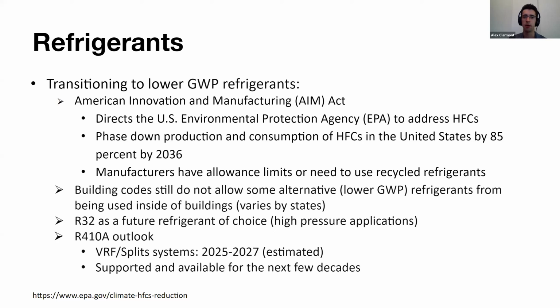Now, one of the issues today is that the prime alternative for R410A is not actually allowed to go through occupied space yet, and that prime alternative for high pressure applications is actually R32. Now, I do mention high pressures because for low pressure applications, this isn't as much of a concern. But for high pressure, that's really the refrigerant you need to do heating. But currently, again, we can't have R32 through occupied space, and it's going to be a few years before that's allowed at a federal level, and then a year or two to get adopted by states. Our estimate is that we're still probably 5 or 6 years away from seeing R32 in VRF systems in large air source heat pumps. And R32 has actually already started for small split systems for residential applications.